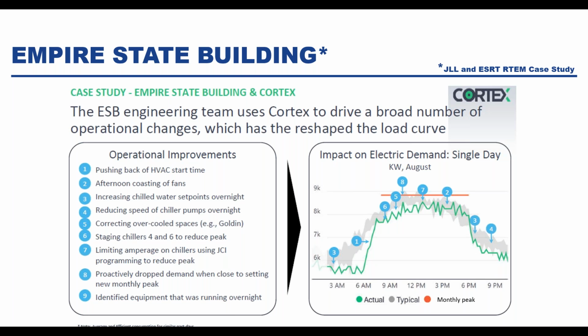The Empire State Building engineering team used this Cortex system to drive a broad number of operational changes. This chart shows a couple of those and how they drove down the load curve to optimize for that specific building and its use cases. They recommended pushing HVAC start time based on what's going on in the building each day, ensuring the building never sets a new monthly peak, since demand charges in New York City can be the majority of energy spend in large buildings like this. It corrected overcooling in certain areas, so tenants are happier, and they turned off overnight vampire loads identified through this system. They're making recommendations on a dynamic, continuous basis and automating processes that drive persistent savings.